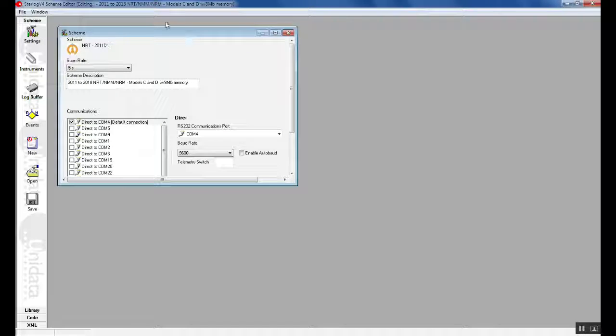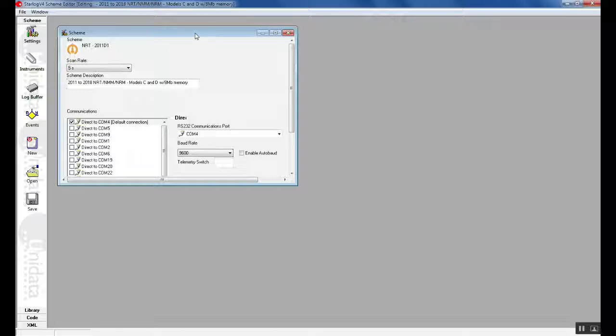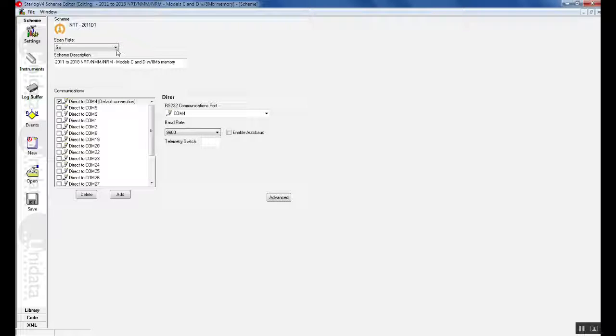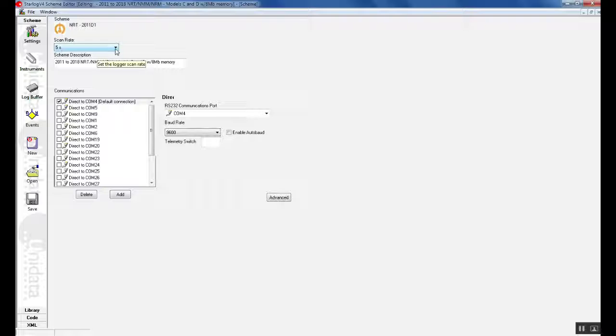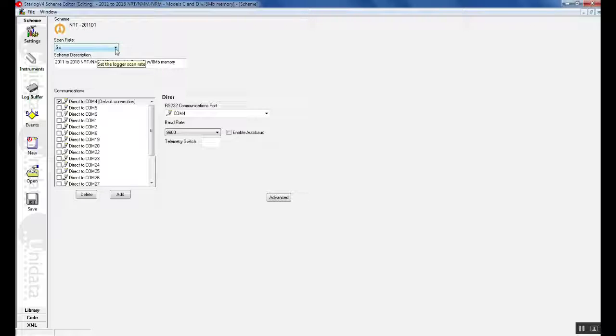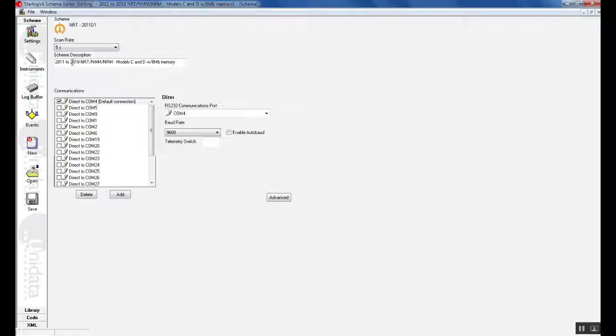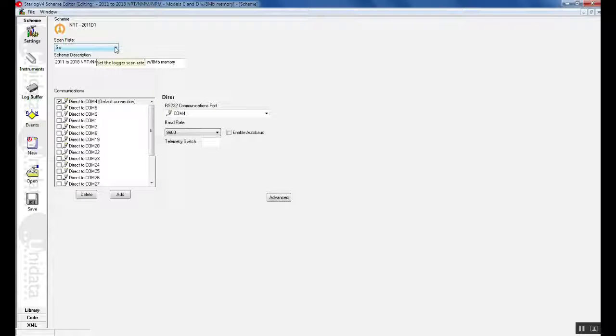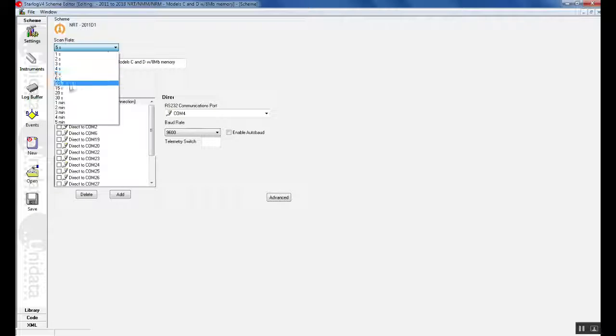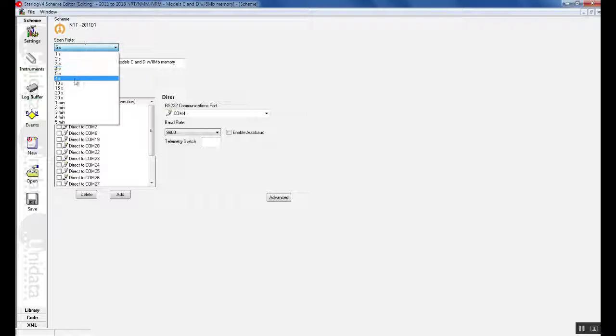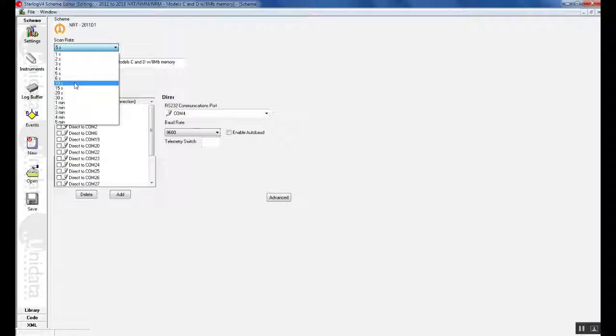We now have a new list of functions down the side. First step is to go to settings. Under the settings window we can configure our scan rate. The scan rate is usually used for averaging values over a period of time. It also wakes up the logger every time during this scan. For general settings the scan rate is usually set at 5 or 10 seconds. Today we will set the scan rate at 10 seconds.